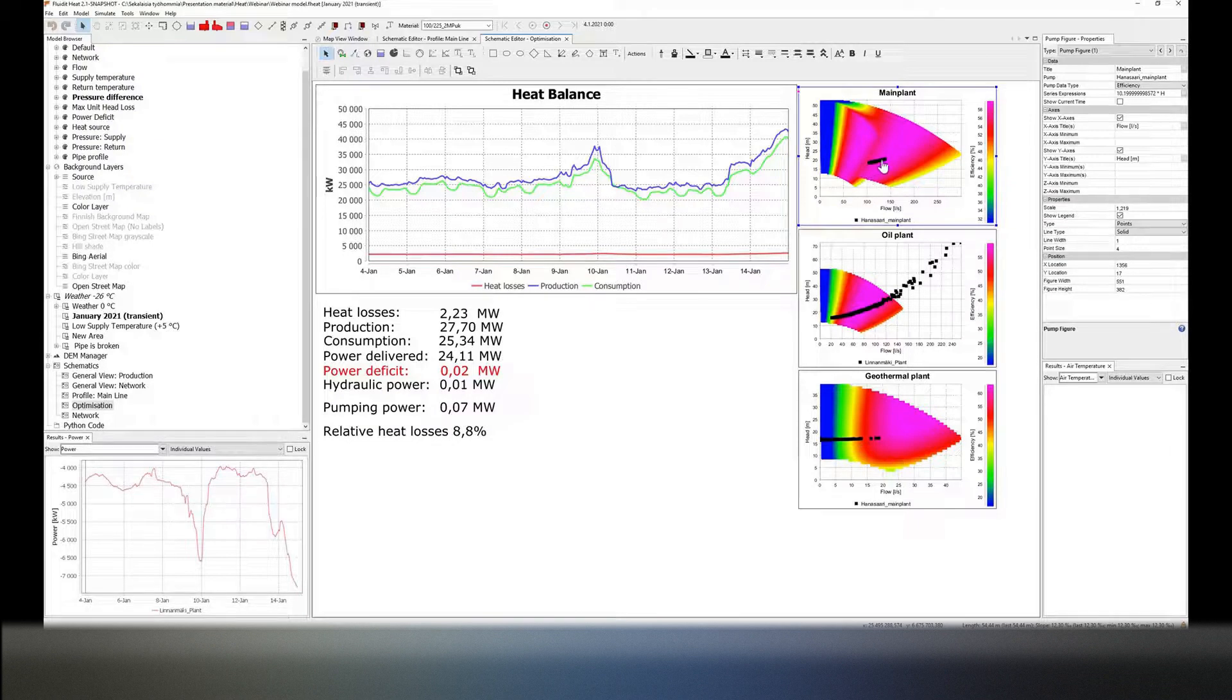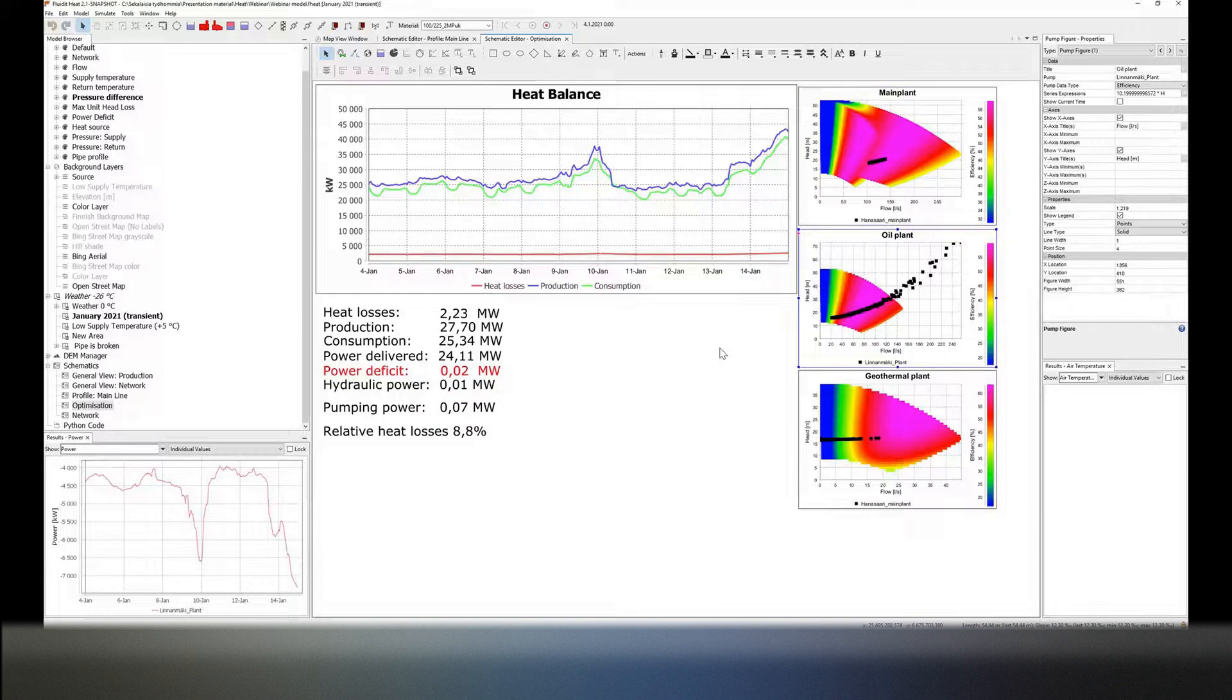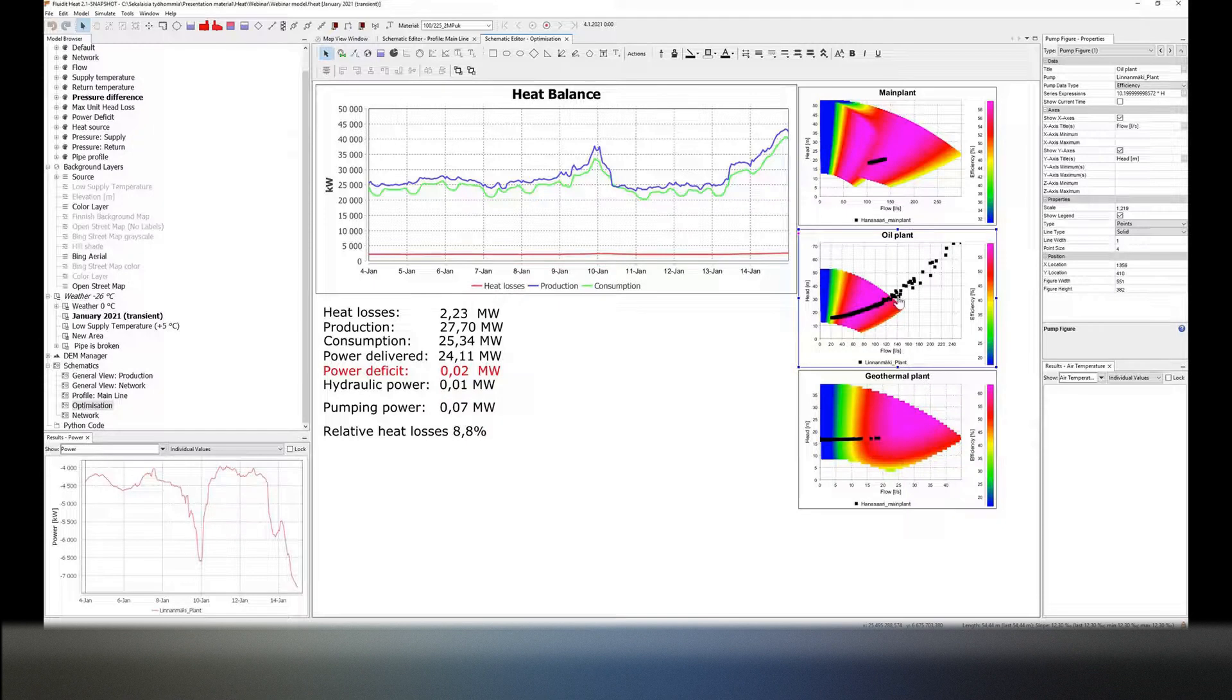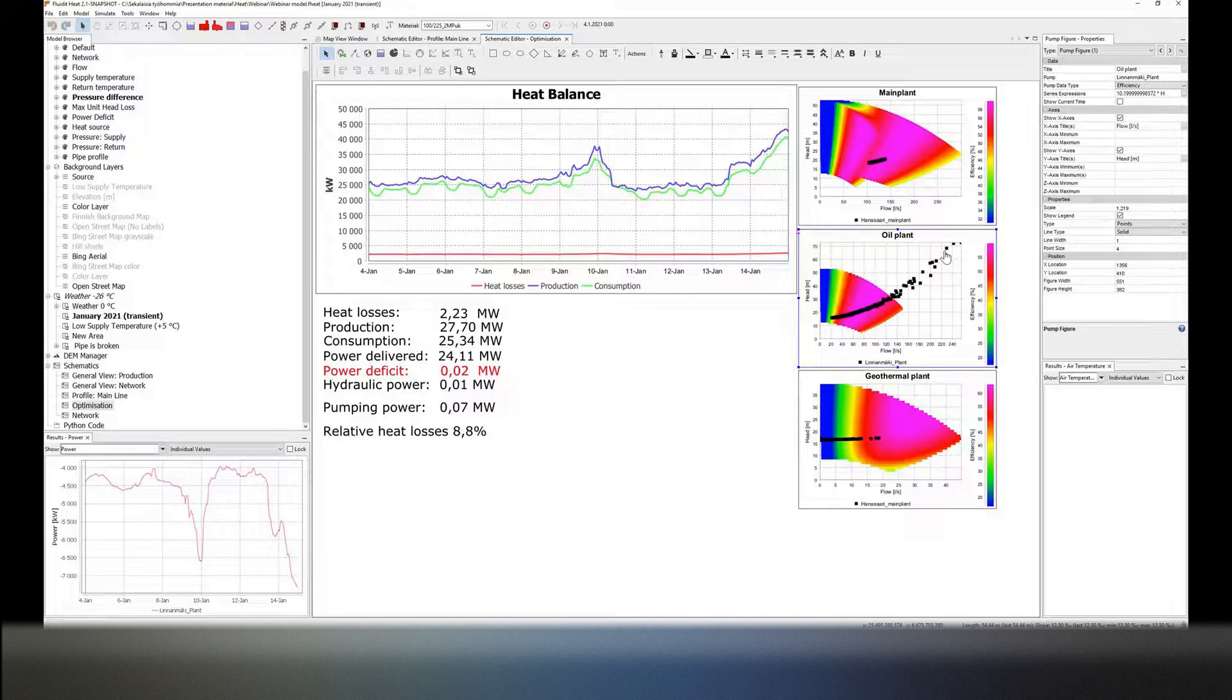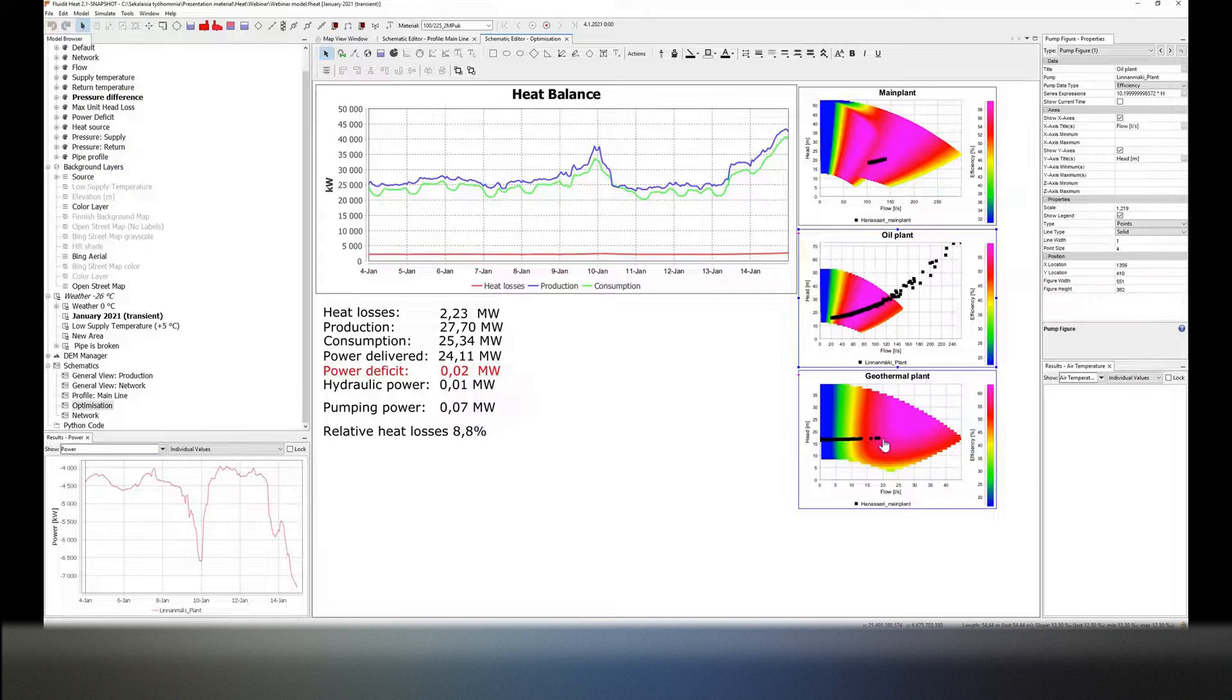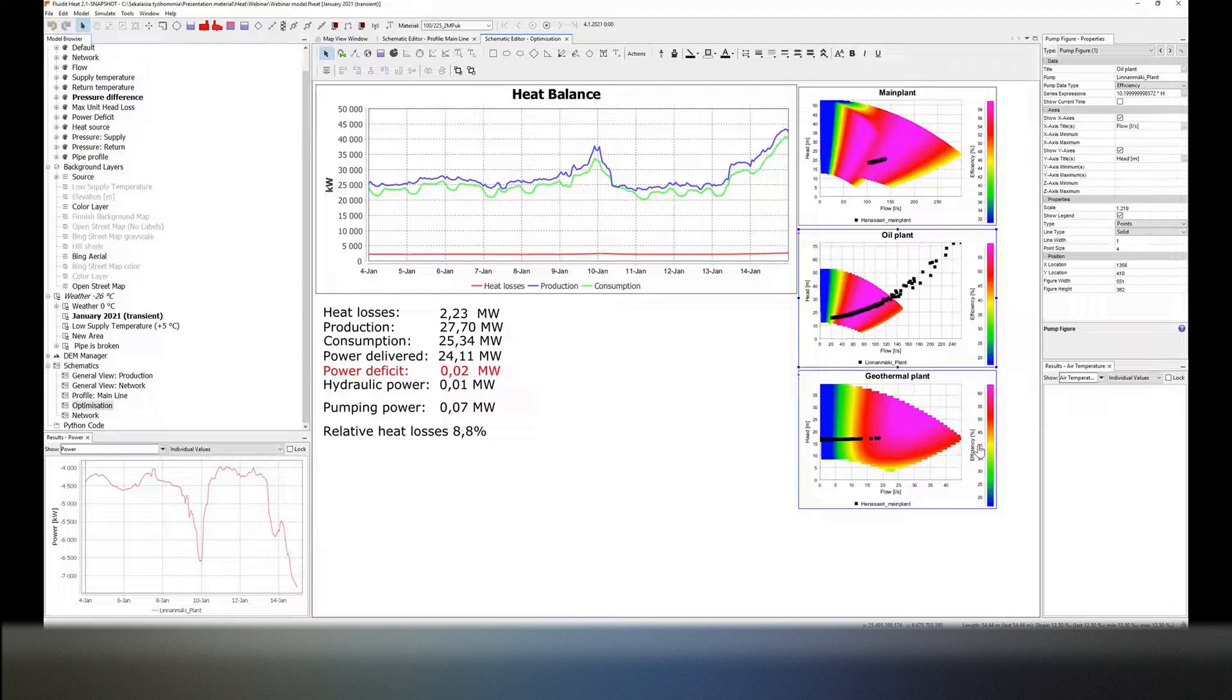So in this case we could notice that our oil plant is running into troubles as this pump - it only has this one pump now - it would have to be functioning at a much higher flow and head than what currently the pump is capable of doing. But what this allows us is to have a very efficient look at the energy usages of the pumps and to do different optimization between the scenarios.